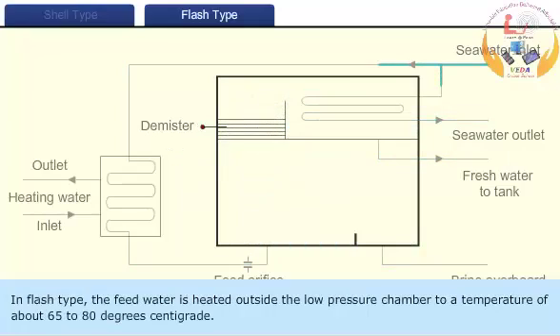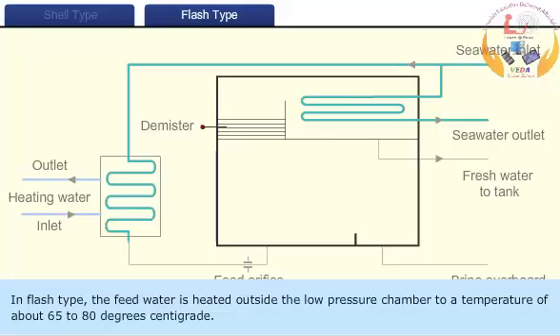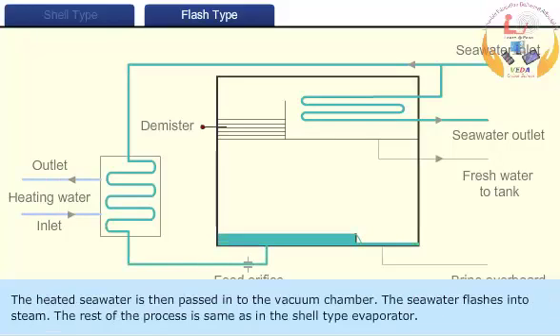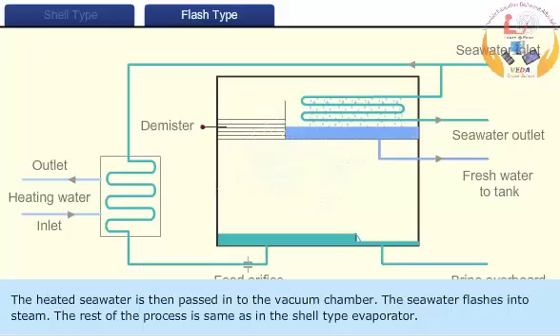In flash type, the feed water is heated outside the low pressure chamber to a temperature of about 65 to 80 degrees centigrade. The heated seawater is then passed into the vacuum chamber, where it flashes into steam. The rest of the process is the same as in the shell type evaporator.